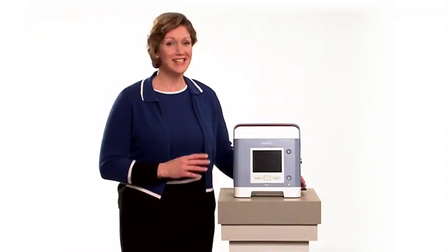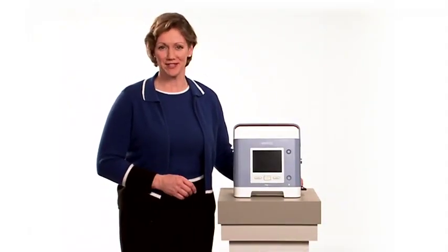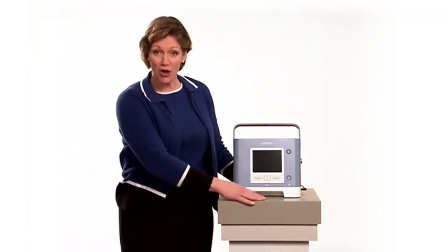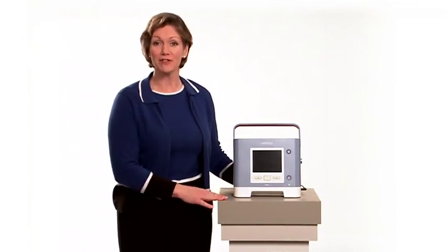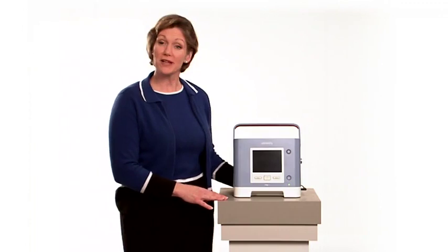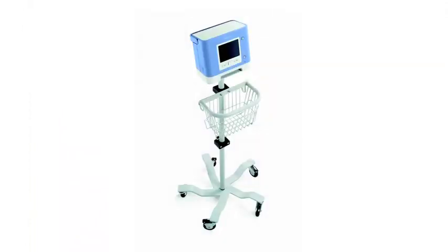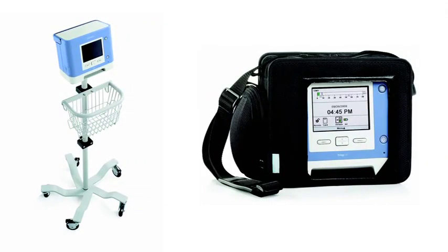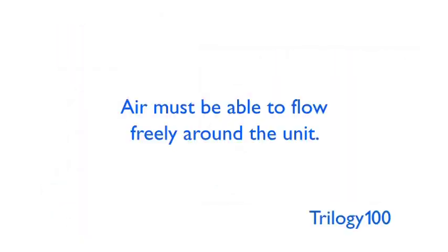Trilogy 100 is easy to set up for home use. Begin by placing it on a hard, non-carpeted level surface. You can also place Trilogy on a stand or set it inside the optional in-use bag. Make sure that the air inlet port on the back of the device is not blocked and that air can flow freely around the unit. If the airflow is restricted, the ventilator may not work properly.